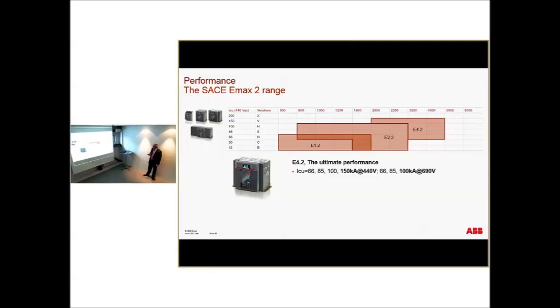The E4, again, breaking capacity 150 kA at 440 volts, Icw 100 kA. Again, switchboard width 600 and 800 for 3 and 4 poles. You have a fully rated neutral in 4-pole, same as the previous range, up to 4000 amps. The neutral is fully rated. Above that, you can choose between half rated and fully rated.